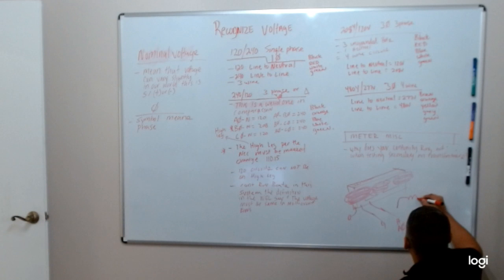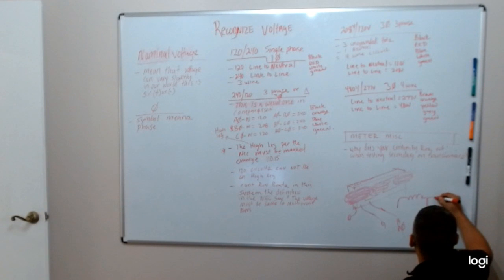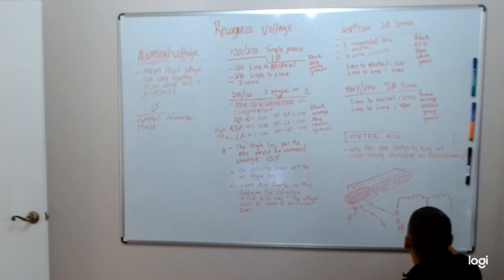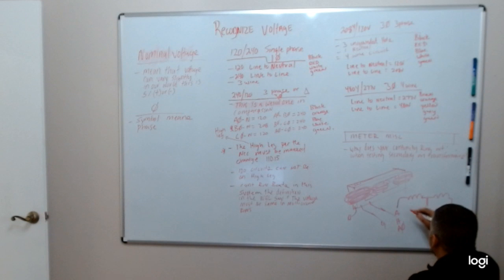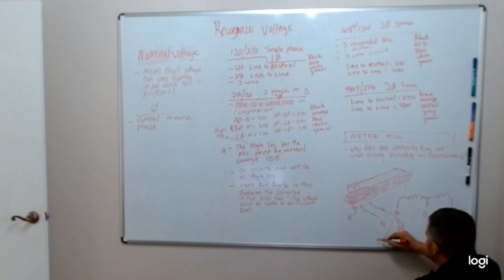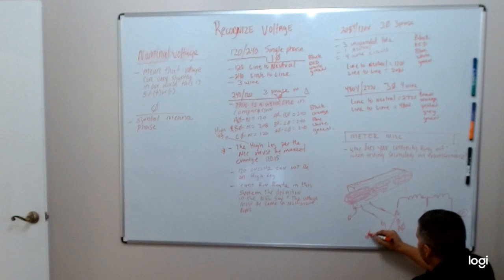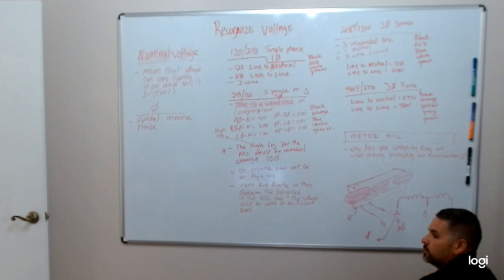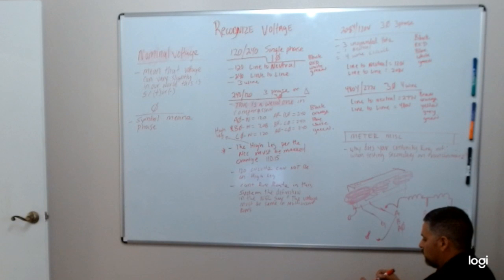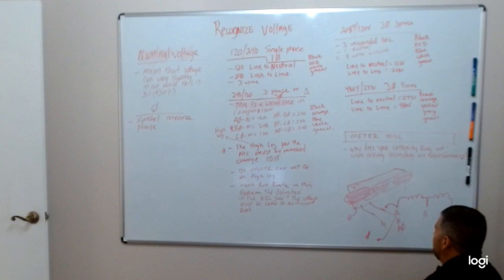So I'm sure you've seen this symbol where it goes like that, and then it's A phase, B phase, C phase on the X0 side, which is your secondary side. Yeah. So what this symbol is basically telling you is that all of this is hooked up together. So when you put one lead on ground and one on your A phase, those will ring out because the transformer itself is grounded. So everything's grounded, connected, dumbing this whole thing down to 120 or whatever it is. So that's why you get that continuity ring out.